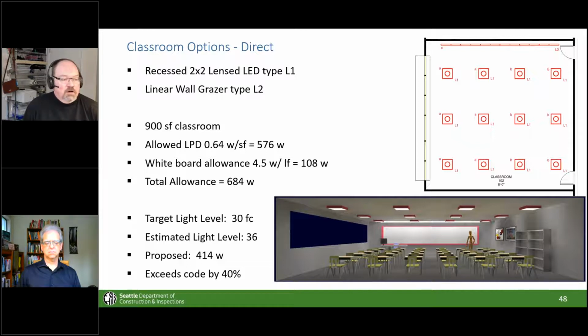So we are meeting our target light level of course, which is 30 foot candles. Our estimated light level here is 36 foot candles. The total allowance is 684 watts. The proposed is 414 watts. So in this particular case, it's exceeding the code by 40%. Now, I would say that if I was designing this, I'd probably give myself a little bit of latitude and maybe only try to beat the code by 20%, as Duane is suggesting. But it is possible to do. Can we go to the next one?